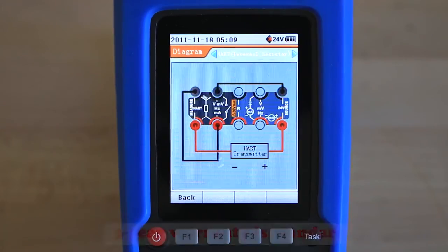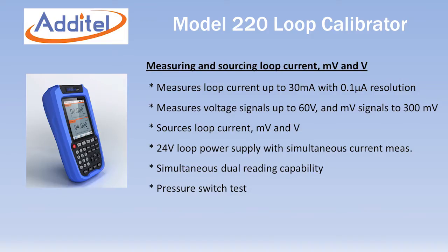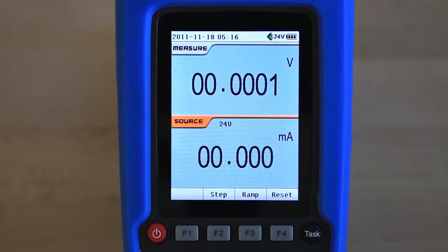Additel also provides a three-year warranty as standard on all models. The Model ADT220 multi-function loop calibrator measures and sources loop current, millivolts and voltage up to 60 volts. An internal 24 volt DC loop supply can be used to power transmitters with simultaneous current measurement.